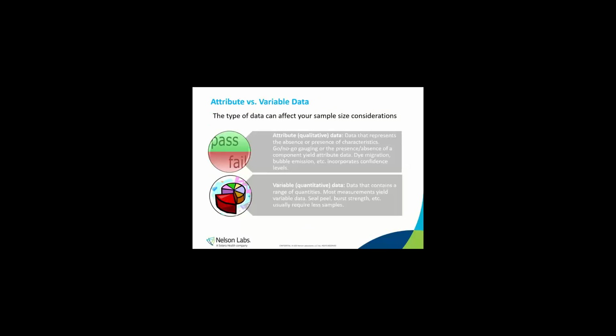I want to touch briefly on attribute and variable data, because this relates directly to packaging validations. Attribute or qualitative data is pass or fail. And so you don't get a numerical value that you can analyze statistically. Tests for package integrity, such as bubble emission or dye migration, are pass-fail tests. Variable or quantitative data is a measured result, and you can run statistics and see how uniform your sample set is. The package strength tests, like peel strength and burst strength, generate quantitative data. Generally, attribute data should have a larger sample size because of the nature of the data, and we usually recommend addressing these two types of data separately in the sampling plan, though that's an individual decision.